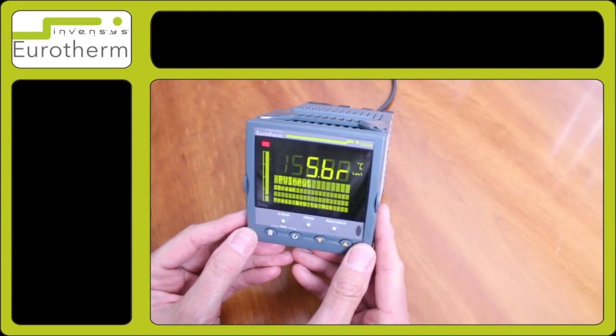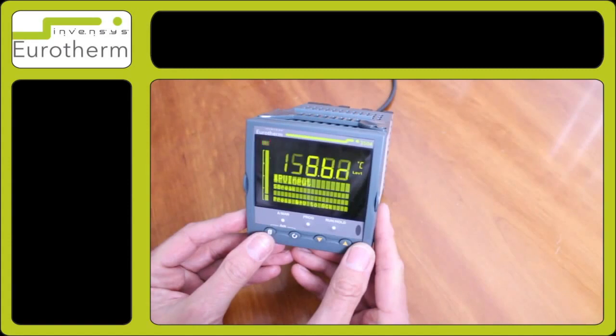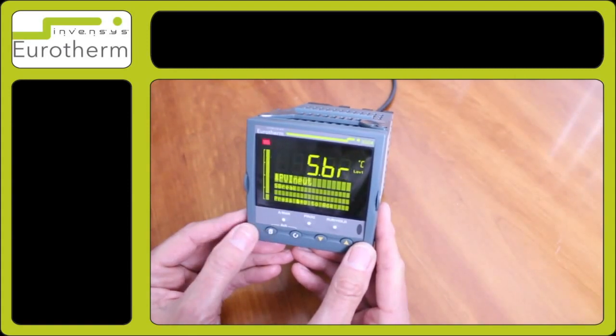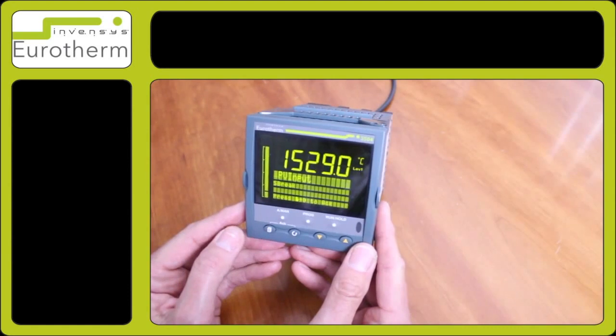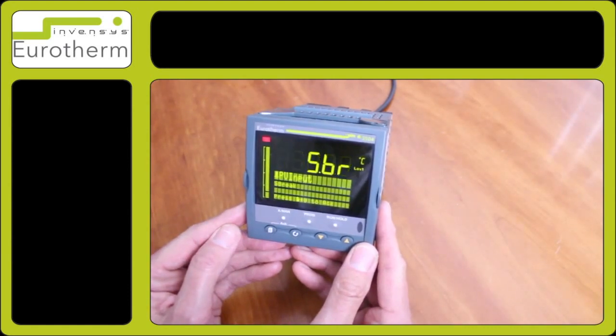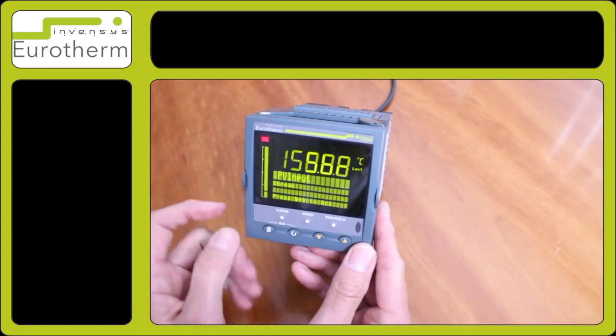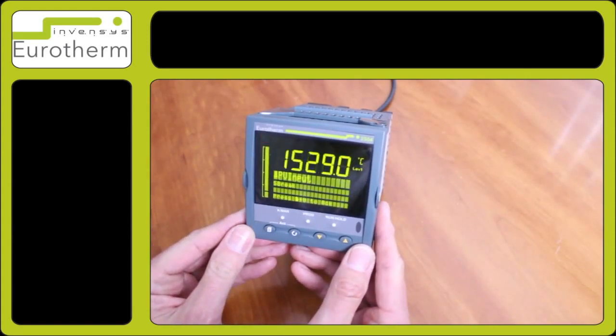In this tutorial I will demonstrate how to test the PV on your 3500 controller, to diagnose whether the input is still working or whether you have a faulty test probe. On this particular instrument, you will see sensor break come up on the screen, S.BR. To test the thermocouple input on the controller, we first need to unpower the unit.